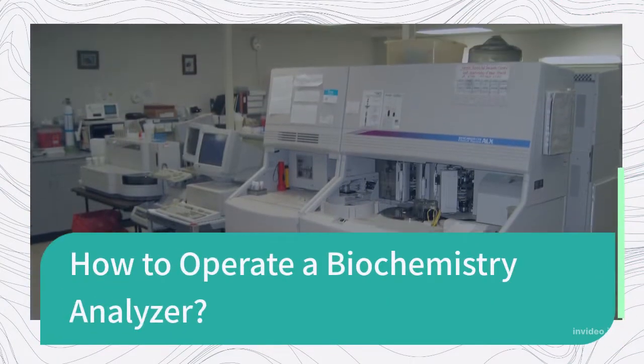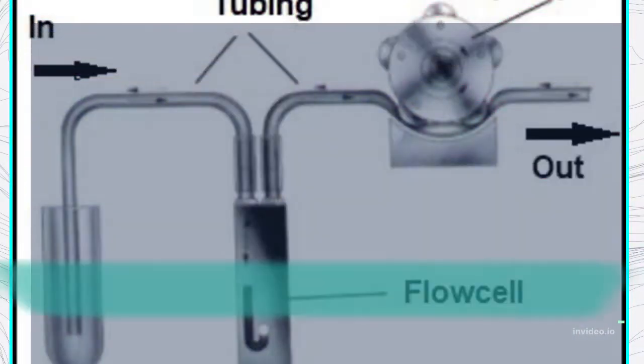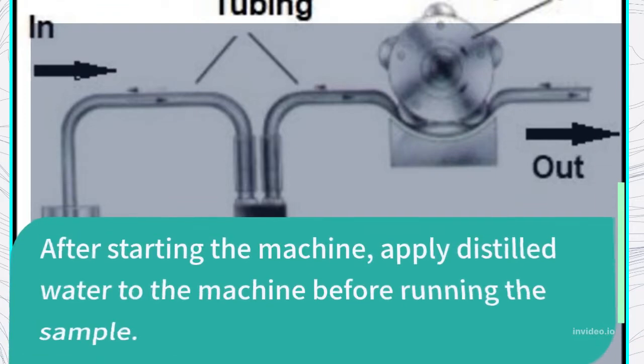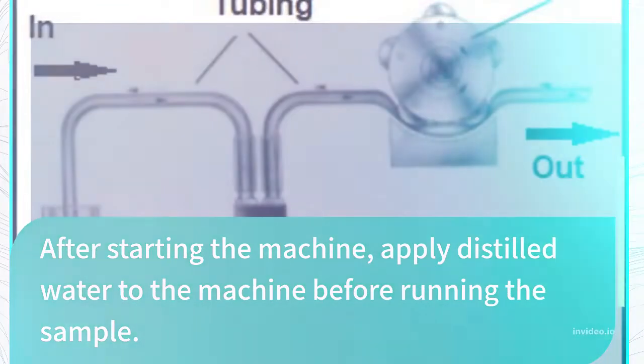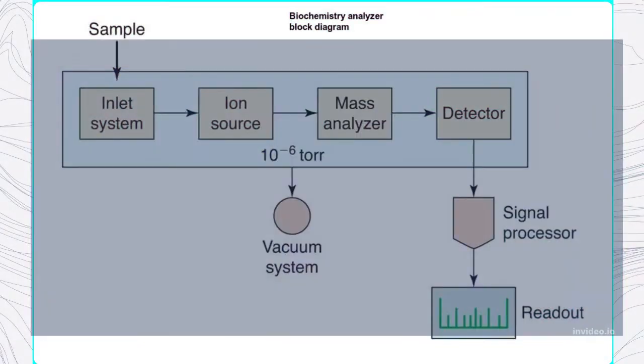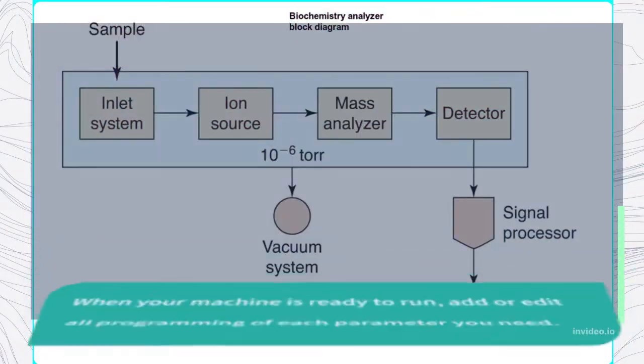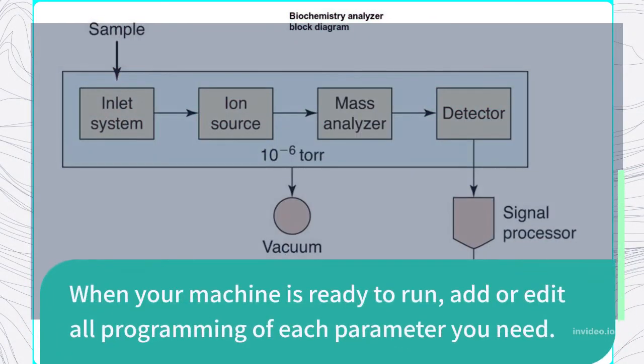To operate a biochemistry analyzer, after starting the machine, apply distilled water to the machine before running the sample. Then be sure to set the standard. When your machine is ready to run, add or edit all programming of each parameter you need.